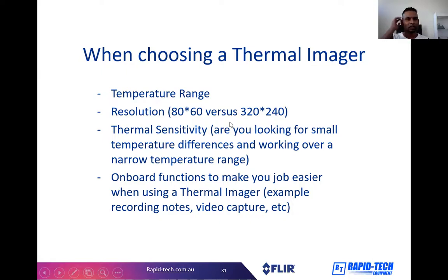Thermal sensitivity, I think, is more important for building applications, because you're working over a narrow temperature range. When you're looking at buildings, you're only working around ambient, and you're looking for very small temperature differences. So thermal sensitivity is a big requirement for building applications or pest work, when you're looking for termites.